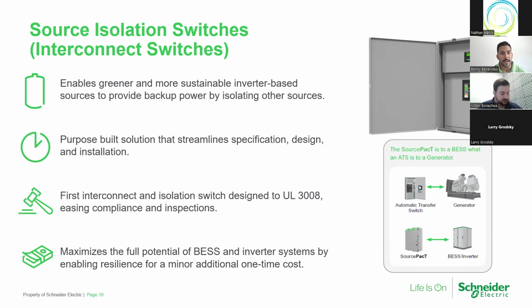Really, it's one of a kind. The first interconnect and isolation switch designed to UL 3008. So new testing criteria to showcase its robustness and rigor in the design criteria. And if you're considering incorporating an energy storage system within your facility with PV, you would also want to maximize the backup power resiliency, and SourcePacT enables you to safely isolate and, at a very basic level, have a microgrid controller talk to the inverter system.